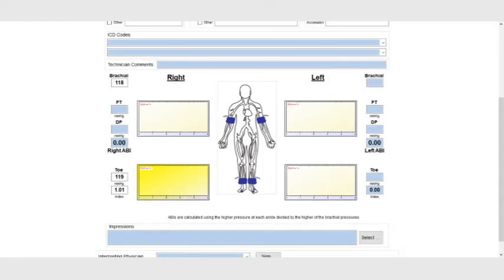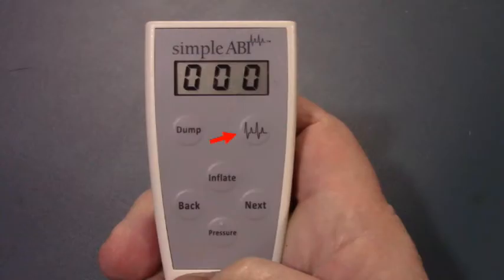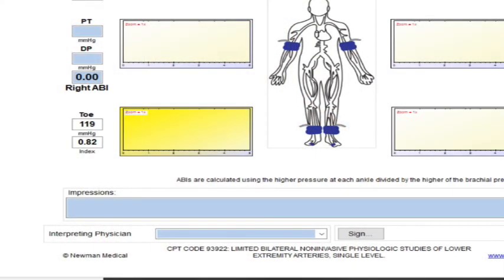Once you have completed the toe pressure, press Next on your remote and the waveform portion of the report will be highlighted. Press the waveform button. The toe cuff will inflate automatically. Deflate to 65 millimeters, hold there, and present the waveform taken. If for any reason the waveform is not acceptable, simply press Waveform again to take a new reading. Once finished, Next will take you to the next pressure to be acquired and deflate the cuff.